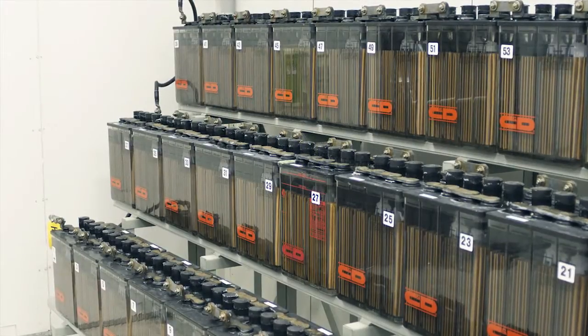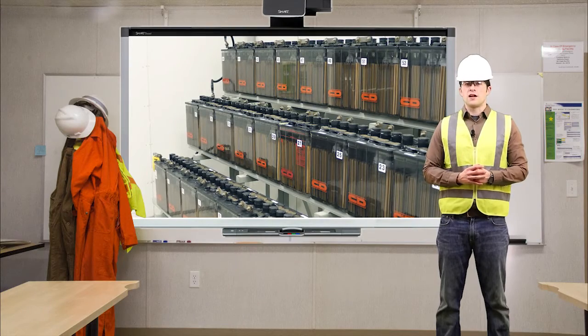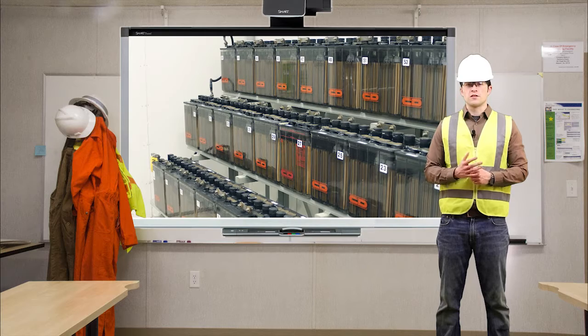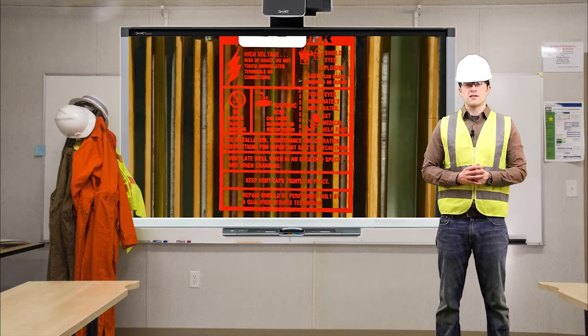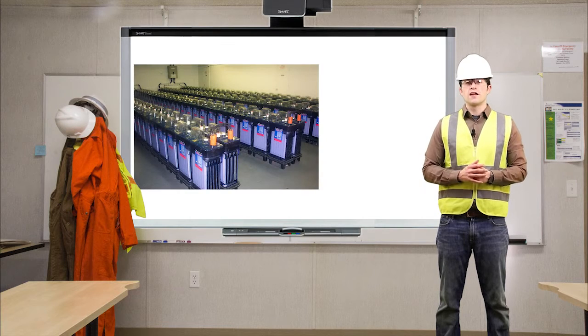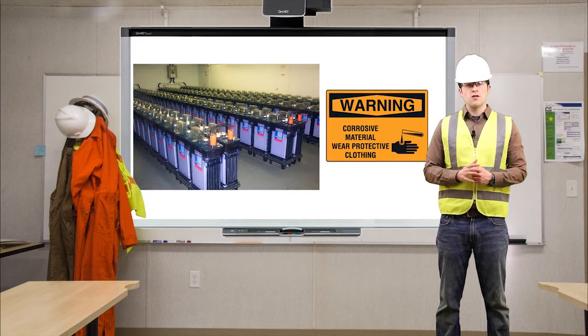Substation batteries are used as a control source, supplying energy to operate substation circuit breakers, relays, and emergency lighting. These batteries store a charge, and you can be shocked even if they are disconnected. In addition, the chemicals that make up the battery's electrolyte are extremely corrosive and can cause serious damage to your clothing and skin.